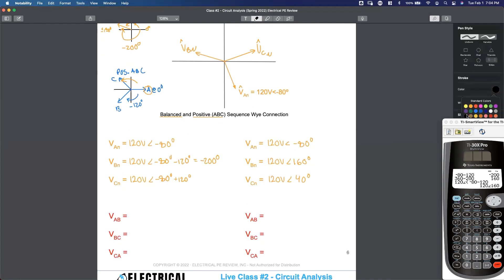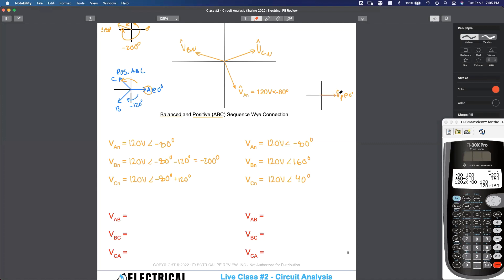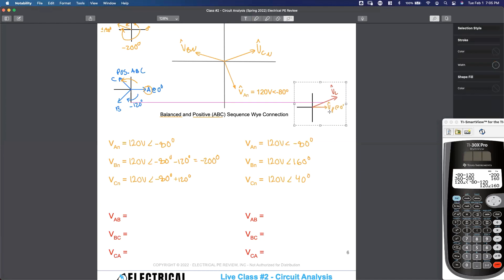Let's draw another phasor diagram roadmap over here on the right side. I'm dealing with a Y connection that's positive sequence. Here's my phase voltage at zero degrees — this could be A phase, B phase, or C phase. How do I go from the phase voltage to the line voltage for balanced and positive? I've got to do two things: starting on my phase voltage, I got to get bigger by 1.73 — we're multiplying by the square root of three — and we're going to lead by 30 degrees. Here's our line voltage.